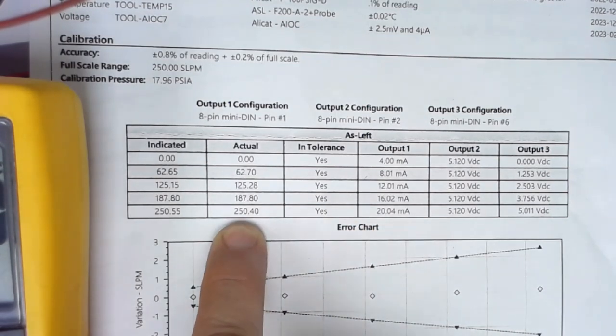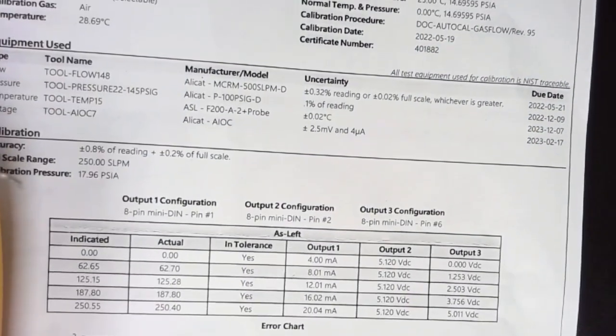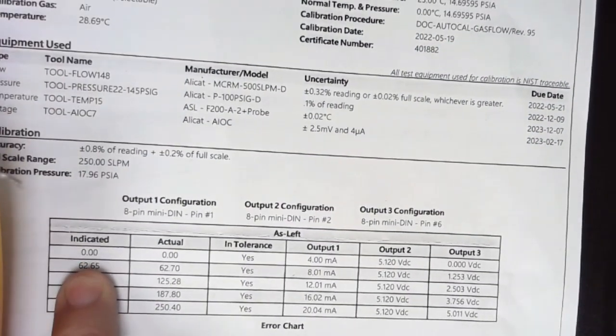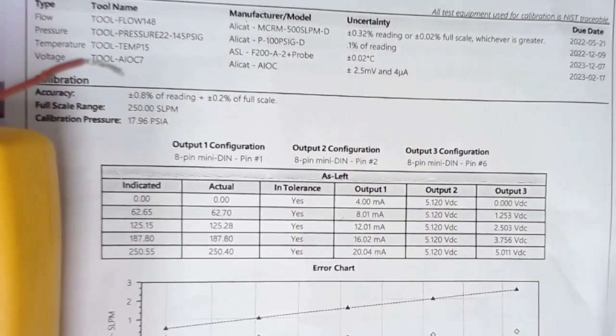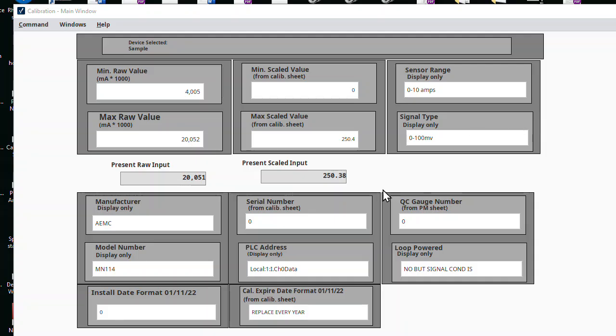That is now my max scale. My min scale is four milliamps and of course zero, but we're going to start with max. I take my calibration sheet and I take those max values. This is the signal I will inject with the meter and this is my max value. I take 250.55 and put that as my max. You'll see I've already done that, so my max value is 250.4 and min is here.